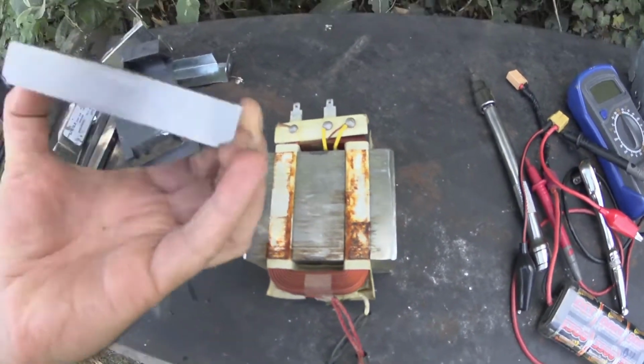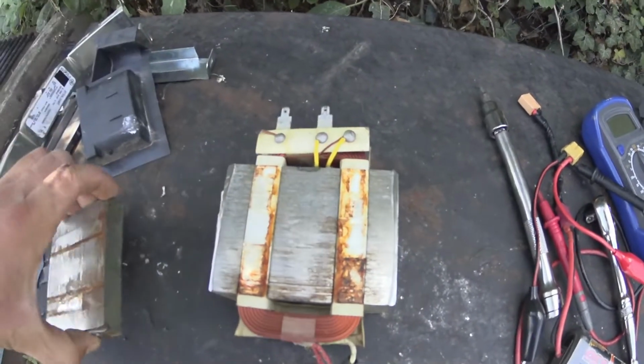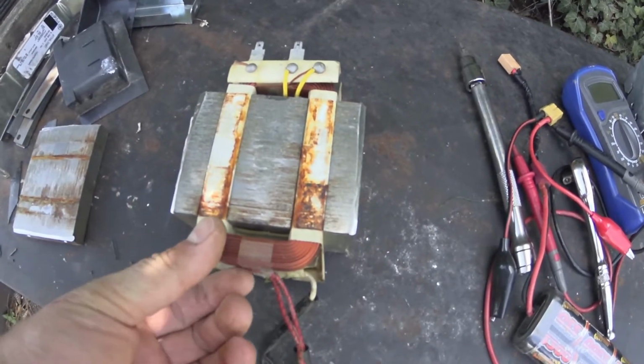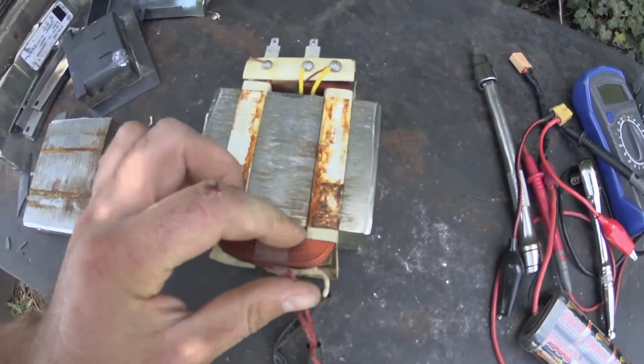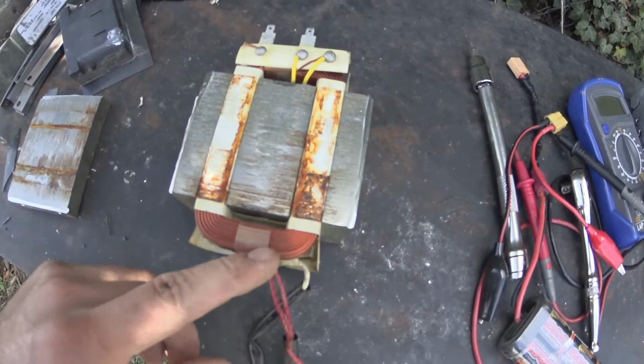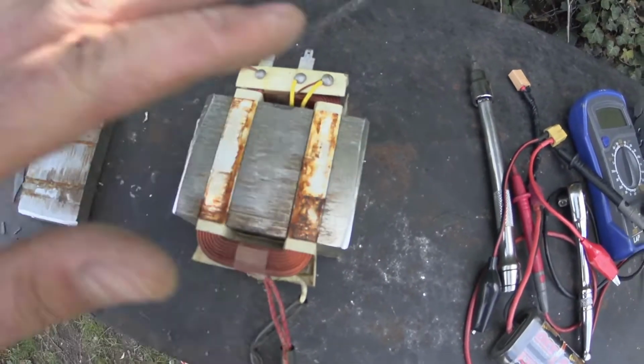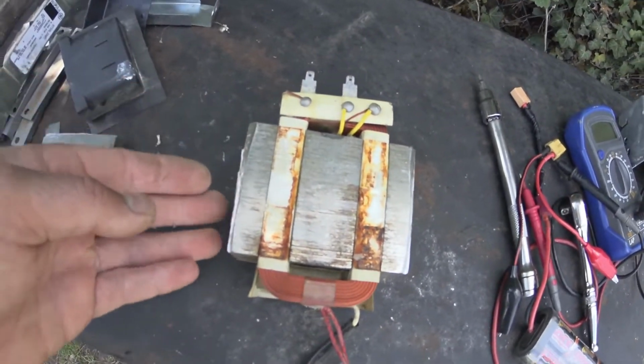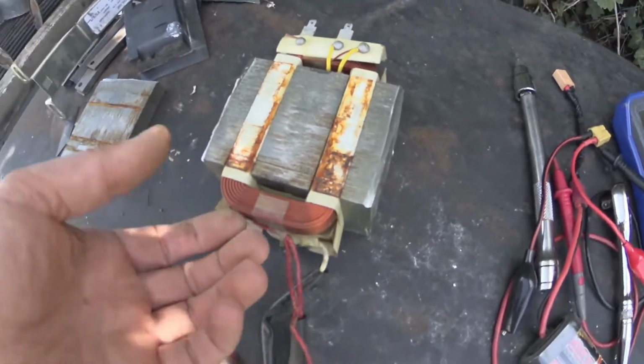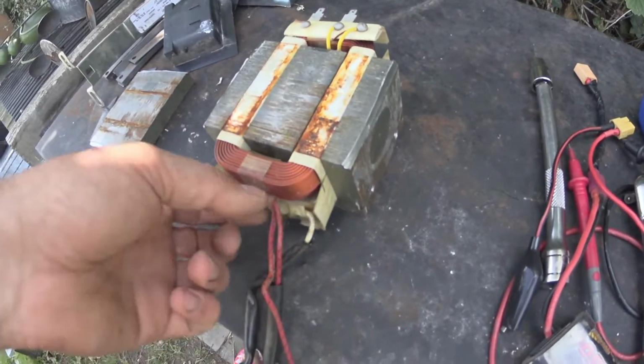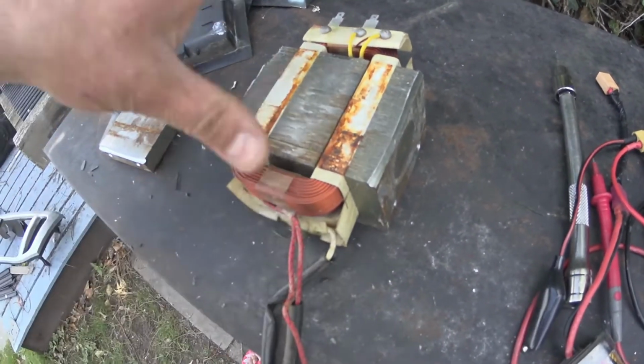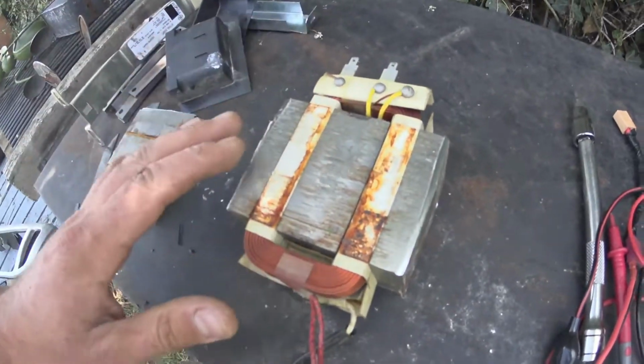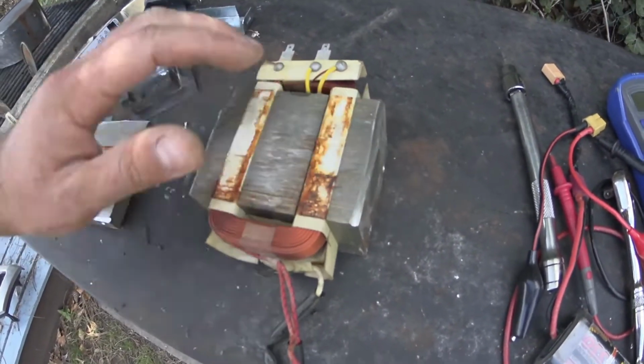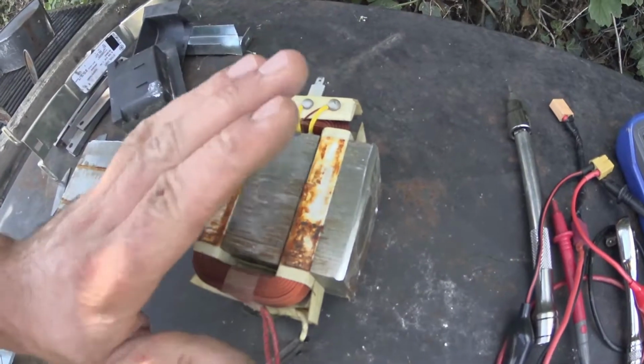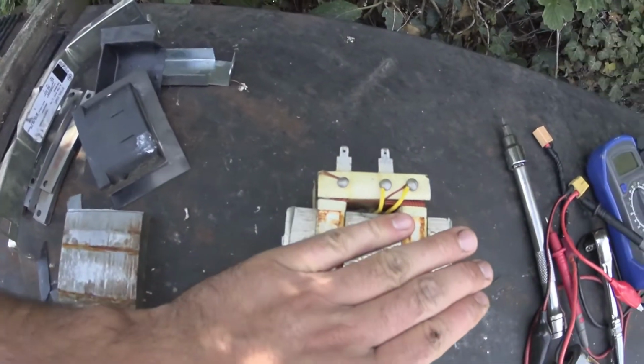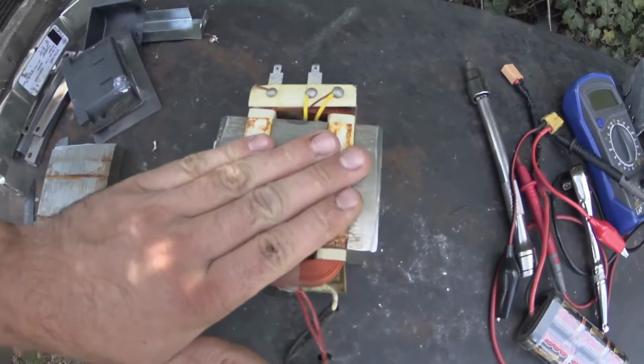Once you've ground that out, tap it off nice and gentle, don't go wallop on these windings, because if you break the insulation between them they'll short out and not be as effective. So what I might do is bust this winding out, the whole high voltage winding, and put this further back down, because if we pick anything up with this it's going to hit these terminals and break them. I'm going to go do that now.